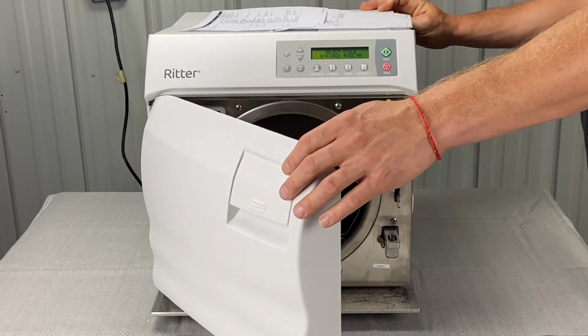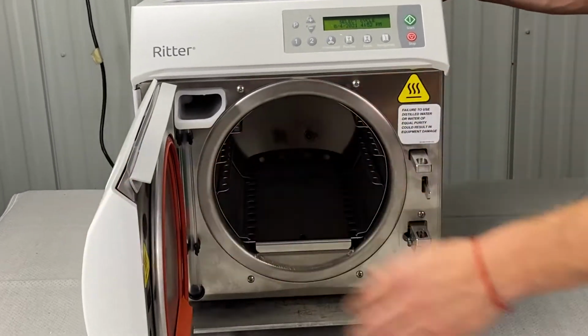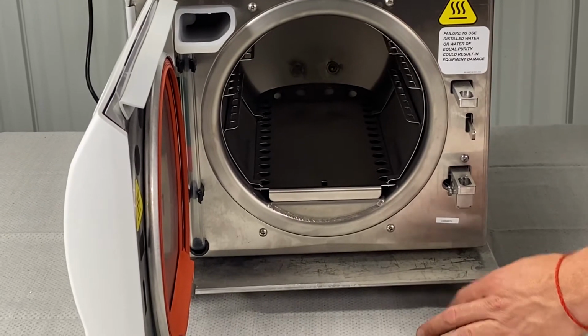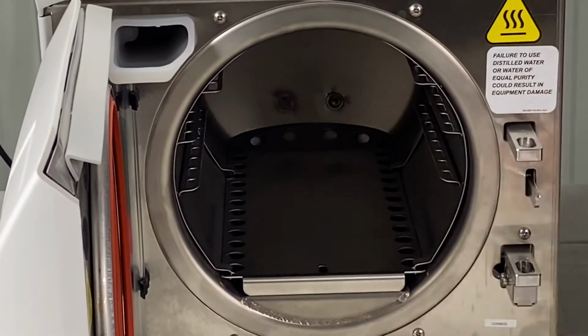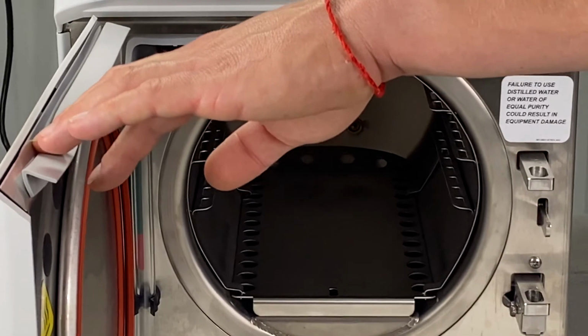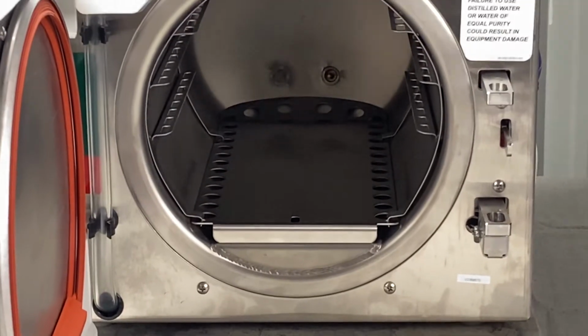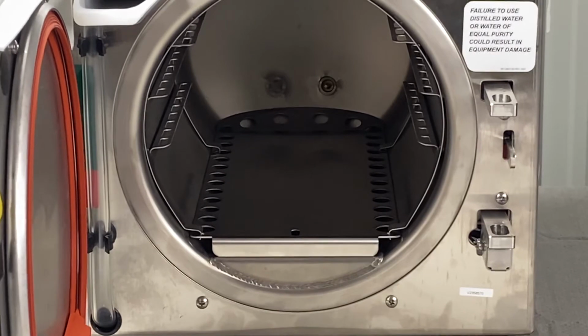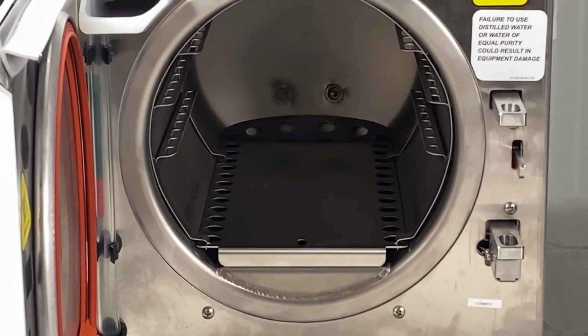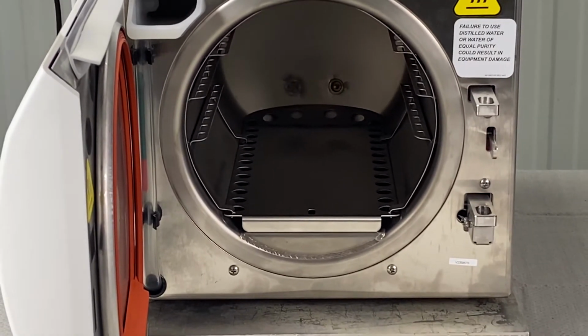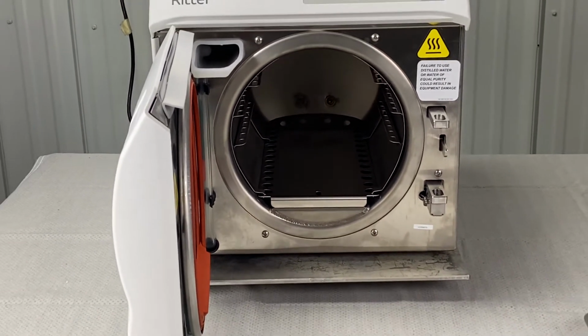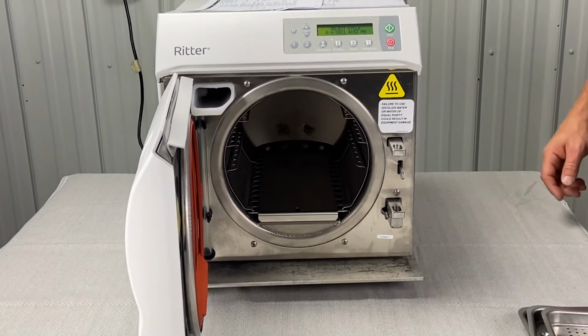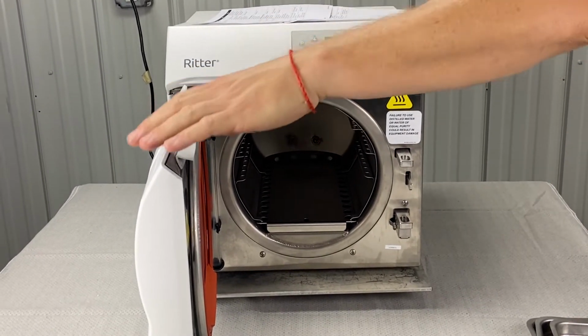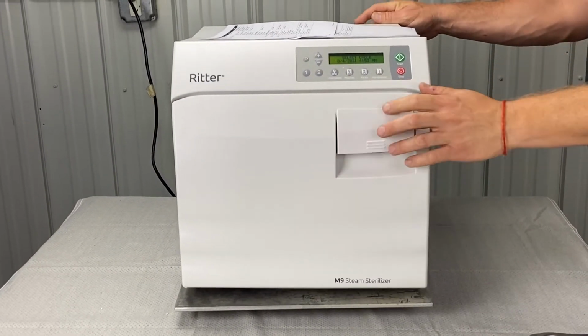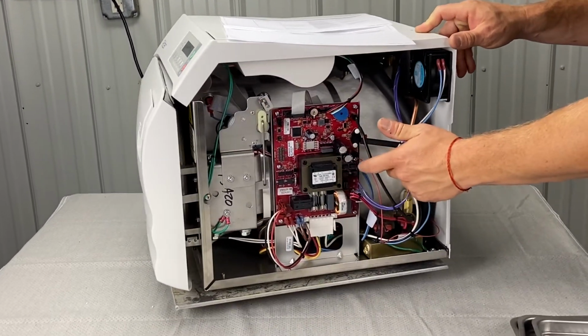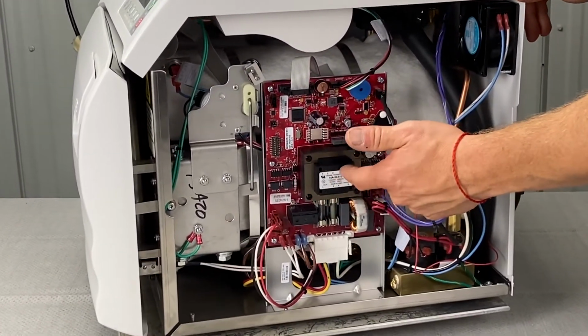Let's see here. It could be the temp sensor is malfunctioning, so that's the reason why we'll run the empty cycle like we talked about in the beginning. The temp sensor is back here. If there's anything touching that, or if there's any buildup or any residue on that, that could cause intermittent 987 overheat issues. It could be faulty itself. If you are going to clean the temp sensor, use speed clean, an abrasive pad, and some distilled water, and then just wipe it dry. That's part of your weekly, monthly maintenance. We might have to perform a resistance test on your temp sensor, an output test on your PC board.